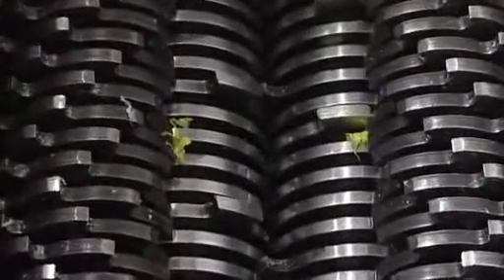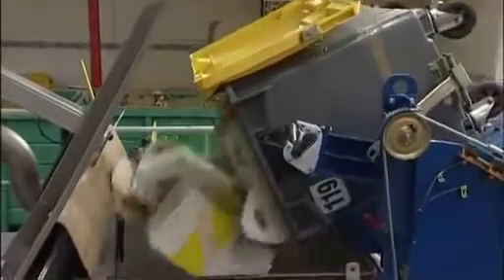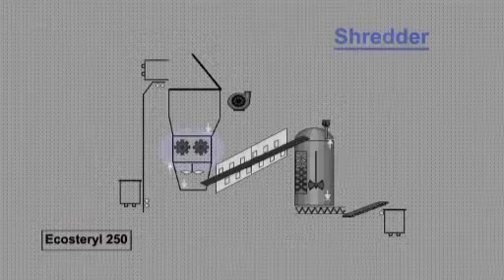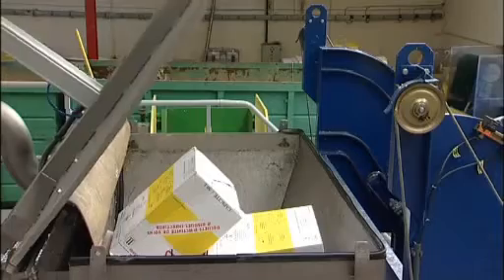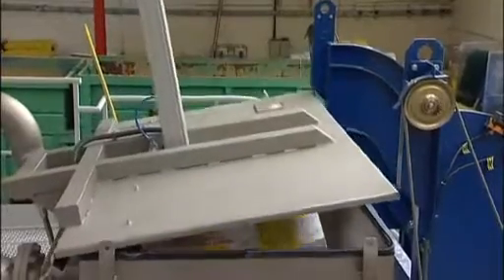When the lid of the loading hopper is closed, the shredder is activated. A screen is placed under the shredder to give a homogenous size under a diameter of 20 millimeters. The very powerful and patented shredder of 37 kilowatts is of the four-axes type, including an automatic anti-blocking device.